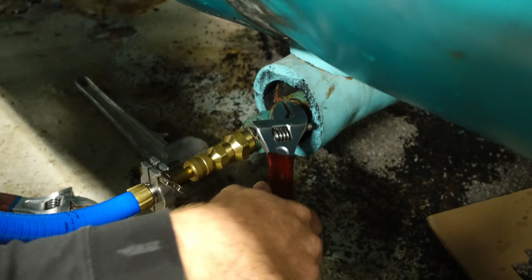Talking to NAVAC, they sent over a bunch of their oil, so I've got plenty of that going forward—I appreciate those guys for doing that. But in discussion with them, what they're recommending in practice is not to base changing the oil off color or anything like that. Their actual practice expects you to get several vacuums out of a single oil fill, and they encourage you not to treat their oil like standard oil, where you'd change it with every vacuum.